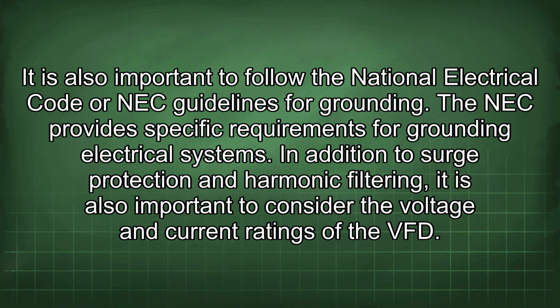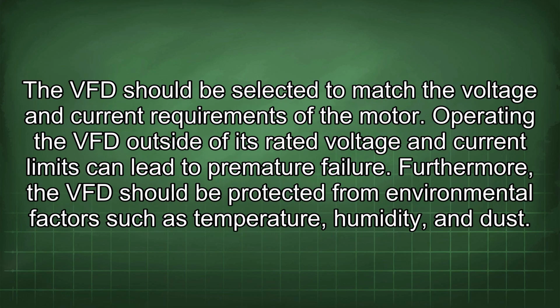In addition to surge protection and harmonic filtering, it is also important to consider the voltage and current ratings of the VFD. The VFD should be selected to match the voltage and current requirements of the motor. Operating the VFD outside of its rated voltage and current limits can lead to premature failure.